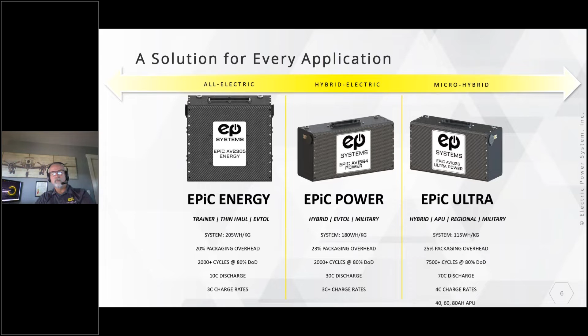So the modules themselves are not a complete battery. They're intended to be put together in series to create a high voltage string. These are meant to be kind of like Legos or building blocks going into a system that would be put together to create strings, and then multiple strings to complete an entire energy storage system. There are some additional supporting elements, but for the most part these modules are fully contained sub-batteries that can be linked together to form larger systems.